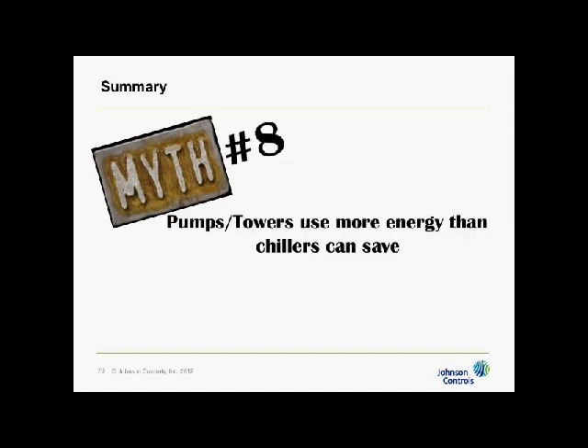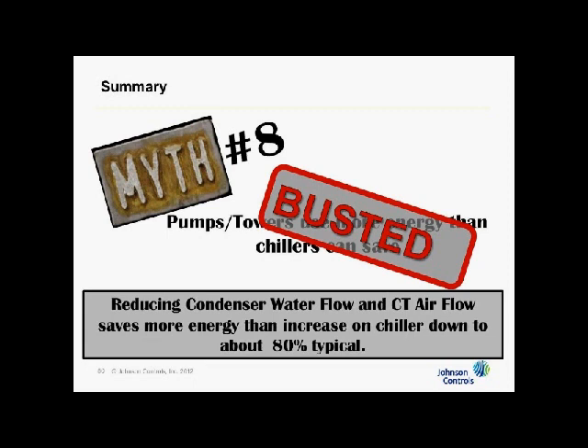Myth number 8, pump towers use more energy than chillers can save. And we busted that. We have proven that reducing condenser water flow and cooling tower airflow can save more energy than the increase in energy on chillers, down to around, at least for the case that we chose, 80% of full design flow.